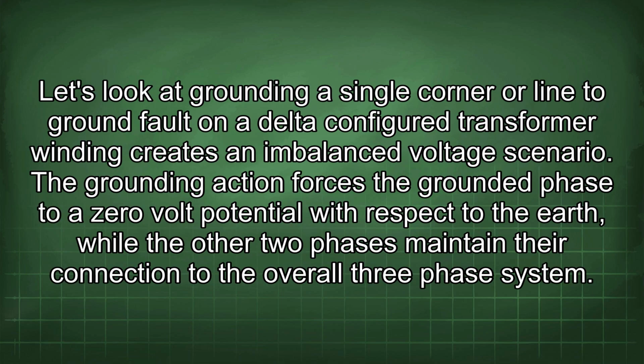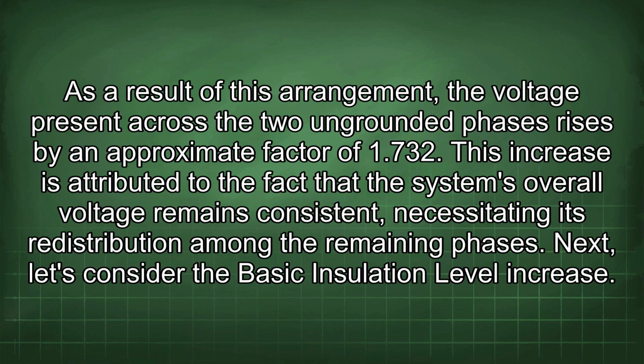Let's look at grounding a single corner or line to ground fault on a delta-configured transformer winding, which creates an imbalanced voltage scenario. The grounding action forces a grounded phase to a 0-volt potential with respect to the earth, while the other two phases maintain their connection to the overall three-phase system. As a result of this arrangement, the voltage present across the two ungrounded phases rises by an approximate factor of 1.732. This increase is attributed to the fact that the system's overall voltage remains consistent, necessitating its redistribution among the remaining phases. Next, let's consider the basic insulation level increase.